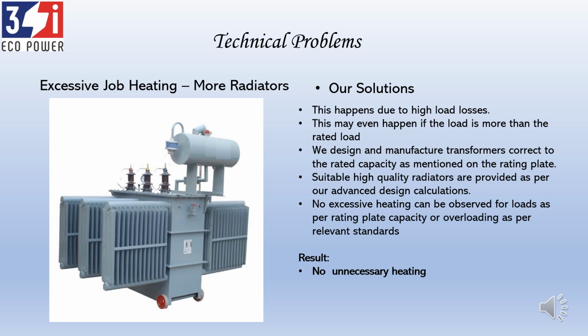A few years back, we offered our transformer for inspection to a client, and the client sent a reputed third-party inspector to inspect it at our works. During inspection, he asked me - your design has very few radiators for the same capacity and specification that your client is purchasing from another manufacturer, and that manufacturer gives more radiators - are you cost saving on radiators? I was shocked by this question, and I explained to him, no sir, it's not like that. Fewer radiators doesn't mean we're cutting cost - we're giving more on copper and core instead.